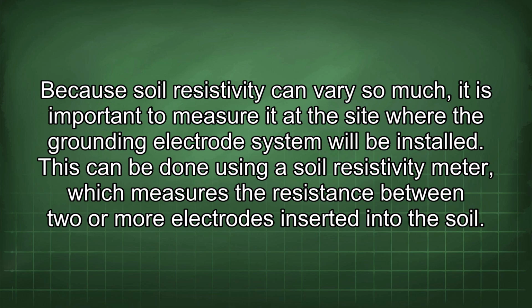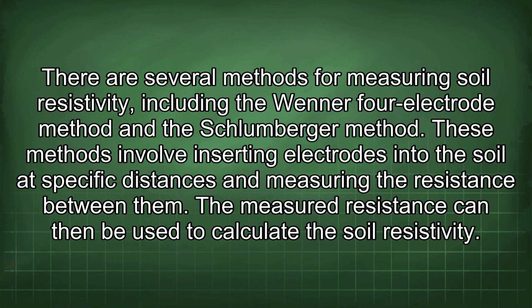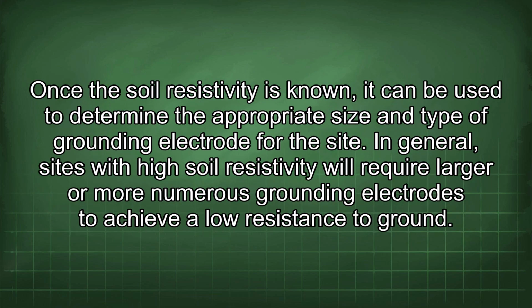This can be done using a soil resistivity meter, which measures the resistance between two or more electrodes inserted into the soil. There are several methods for measuring soil resistivity, including the Wenner four-electrode method and the Schlumberger method. These methods involve inserting electrodes into the soil at specific distances and measuring the resistance between them. The measured resistance can then be used to calculate the soil resistivity. Once the soil resistivity is known, it can be used to determine the appropriate size and type of grounding electrode for the site. In general, sites with high soil resistivity will require larger or more numerous grounding electrodes to achieve a low resistance to ground.